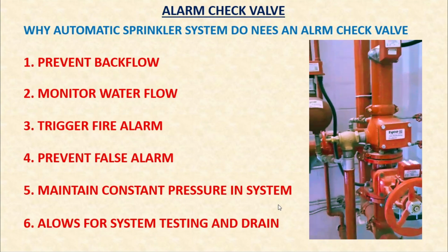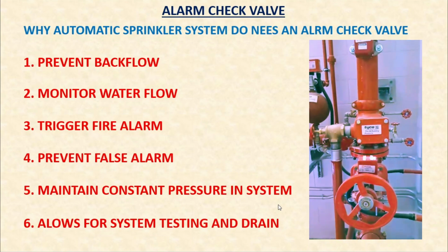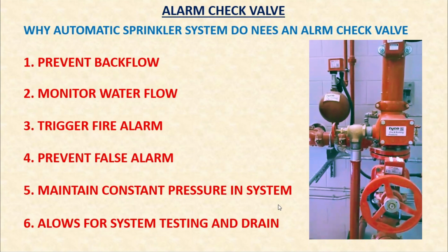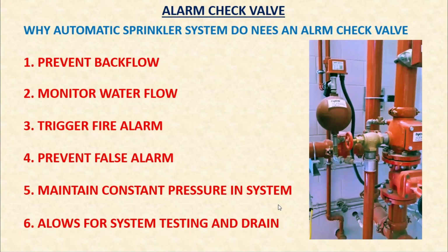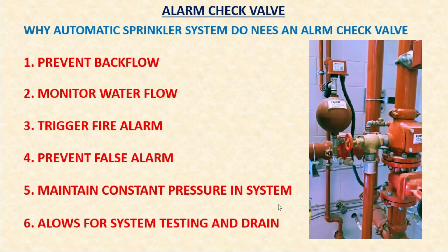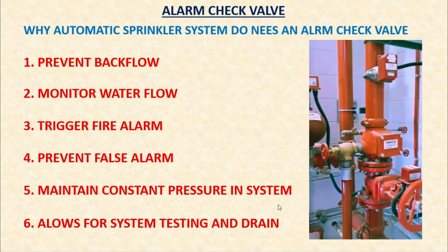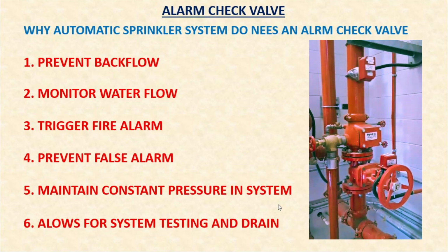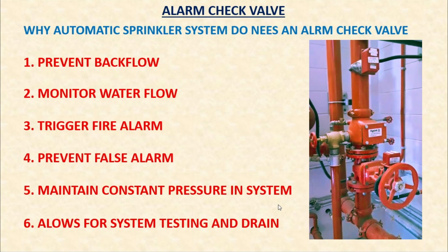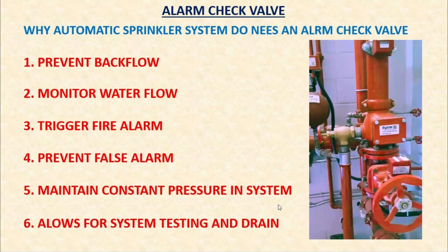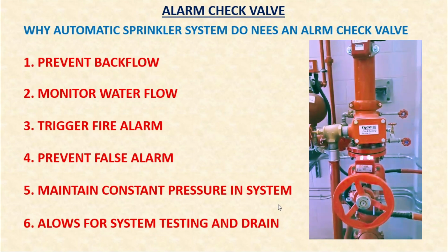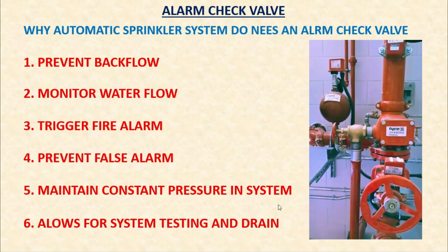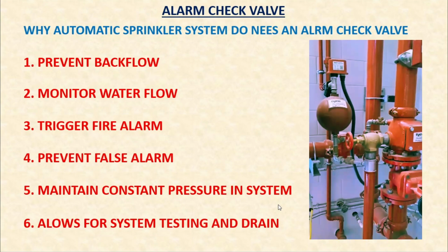Next is it helps in system maintenance and testing. See, the alarm check valve often has a drain valve, as you've seen, which allows maintenance personnel to simulate sprinkler activation and test the alarm system without needing to activate actual sprinklers. So it can also facilitate draining the system for maintenance and inspections.